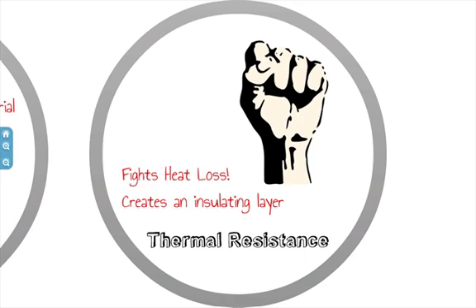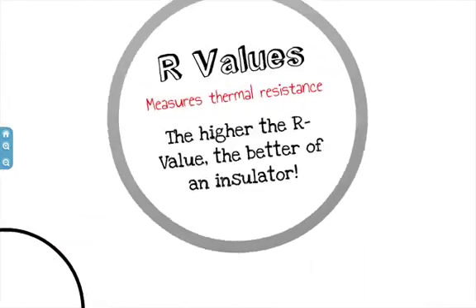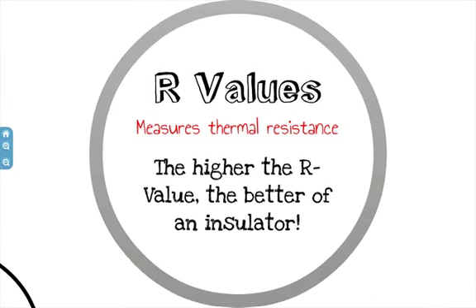Air is the best resistor to heat flow found in buildings. There are other types of things that will create thermal resistance as well, and we call those insulation. R-values measure the thermal resistance of a material — a unit of thermal resistance used for comparing insulating values of different materials. The higher the R-value of a material, the greater its insulating properties, and the slower the heat will flow through it.